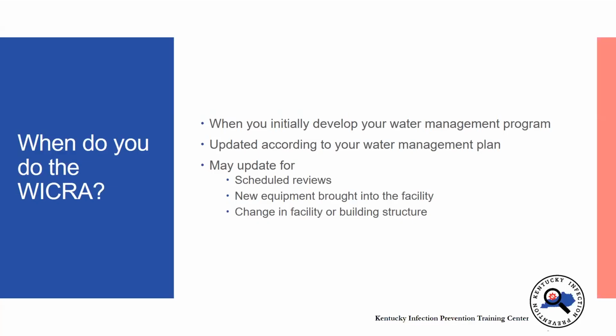So when do you do the WICRA? You want to initially really recognize that this should be a fluid document, okay? So when you initially develop your water management program, you should absolutely have your WICRA. Your water management plan may have prescribed times that the WICRA should be updated, annually or every 6 months, for example. But that is not the only time that the WICRA should be reviewed. You can't just leave it and let it be and think that that is enough.